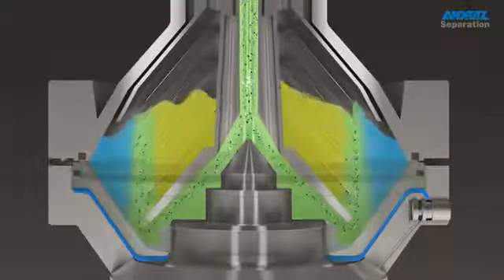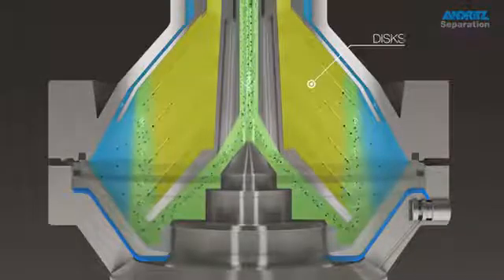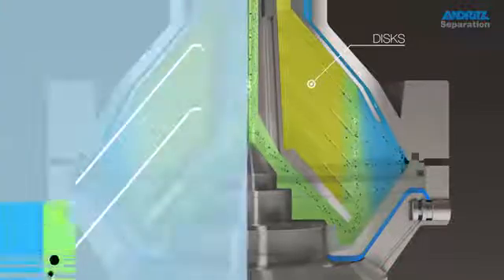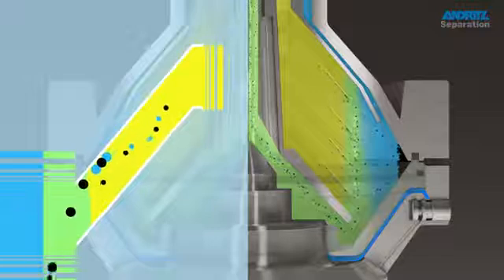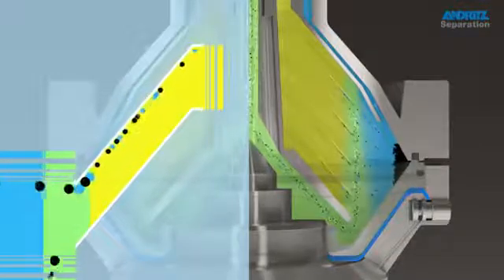Large particles of solids and water immediately move to the periphery of the bowl. Oil with remaining contamination of solids and water enters the space between the disks. Oil with contaminants flows towards the center of the bowl between the disks. Under the centrifugal force, the droplets of water and solid particles will move towards the lower surface of the disk.